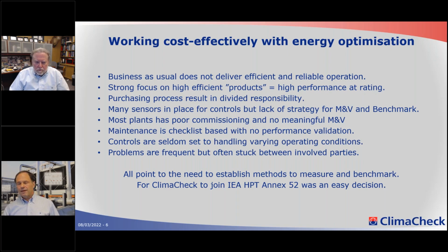And maintenance, then, this is normally checklist based. Somebody goes out and fills out the list, and many times they force the system to run for a short period of time. This does not give anything useful for validating performance.